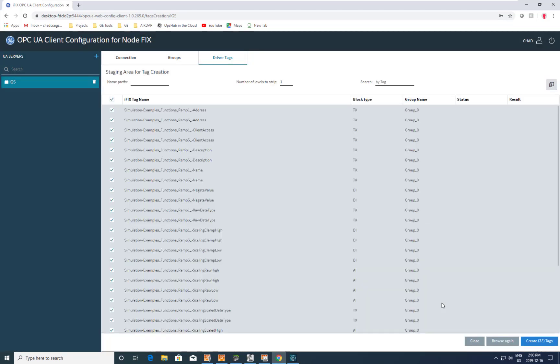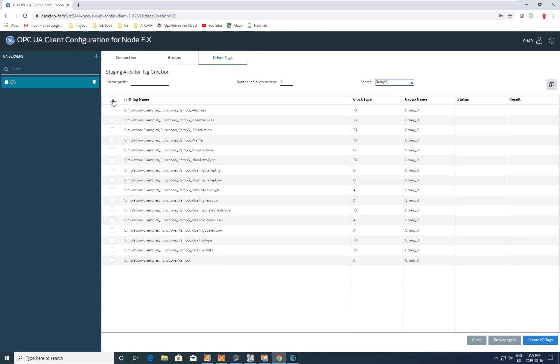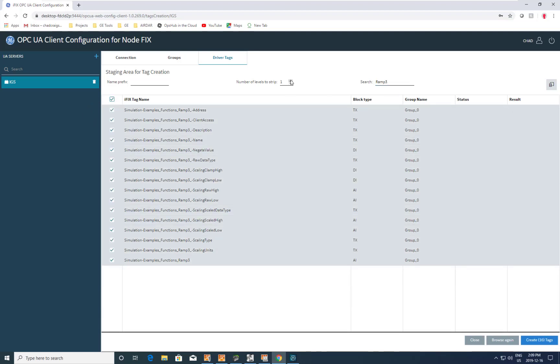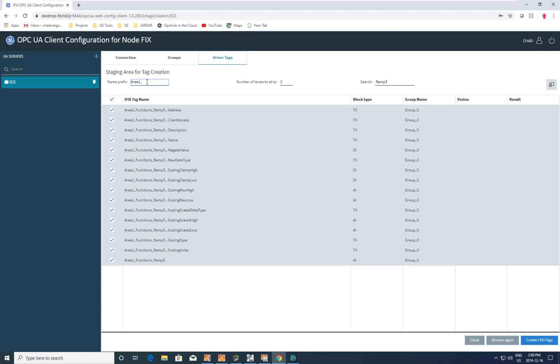We can stage those tags and decide to filter them. For this purpose we're only going to create tags associated with ramp 3, so you can see all the tags on ramp 3. We're going to strip off the front level of the hierarchy and put a prefix on there — we'll call this 'area1_'. You can see it tacks onto the front, so these are the tag names that would be created in iFix.